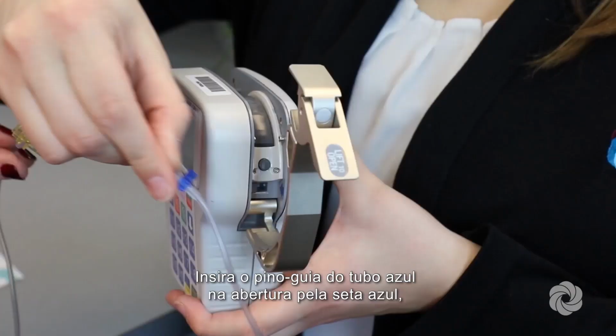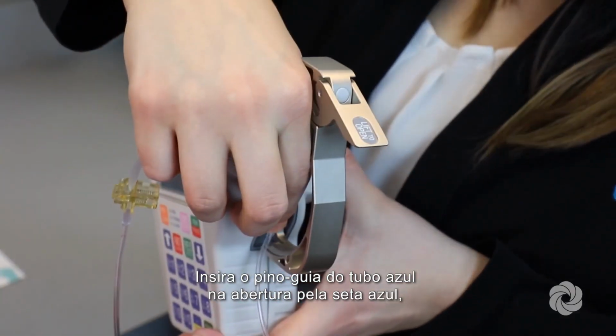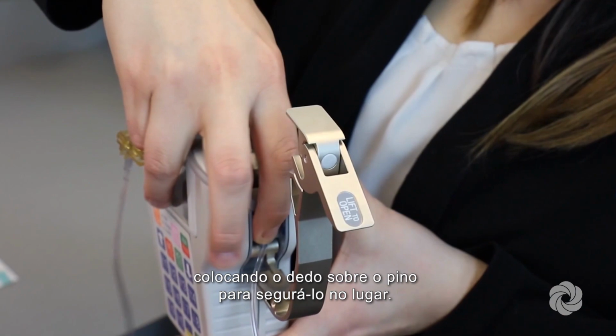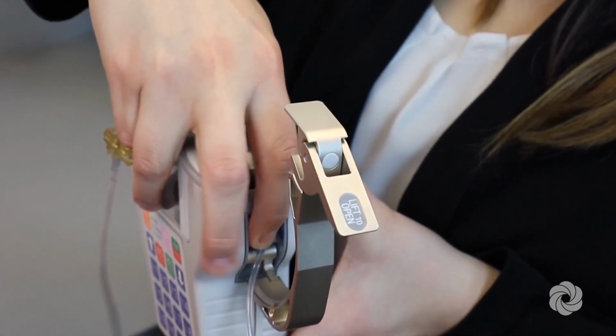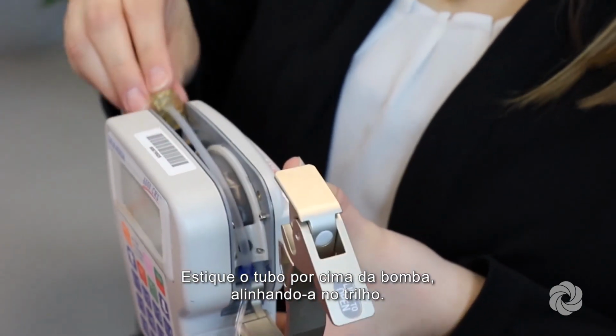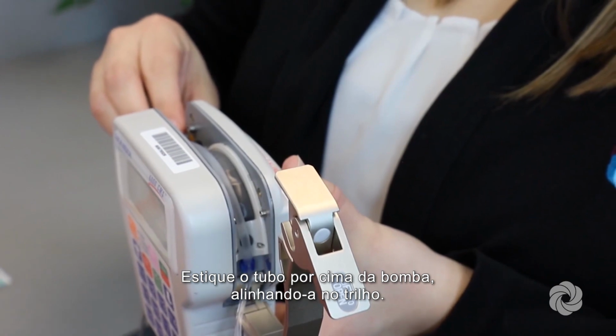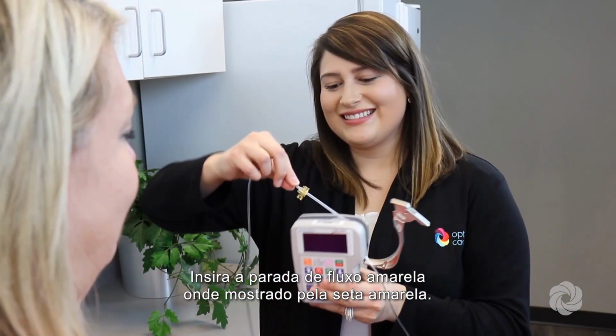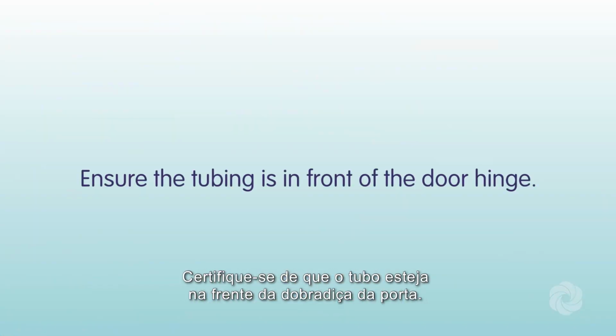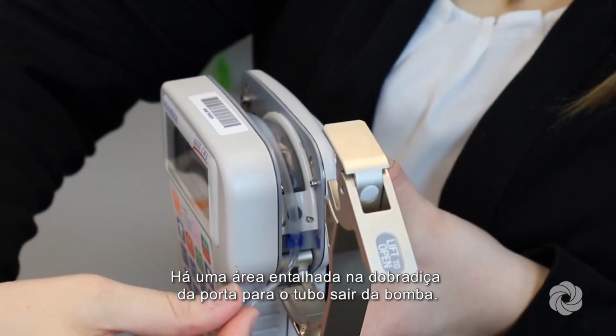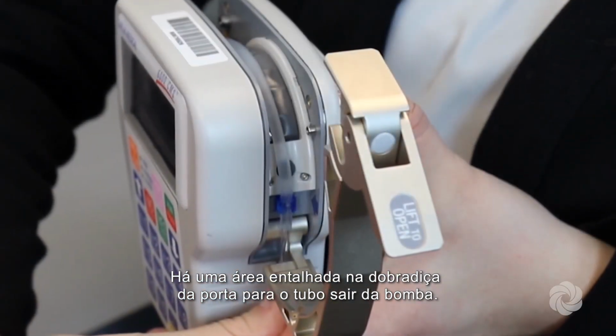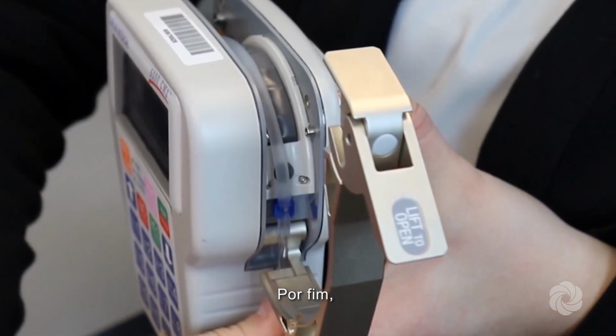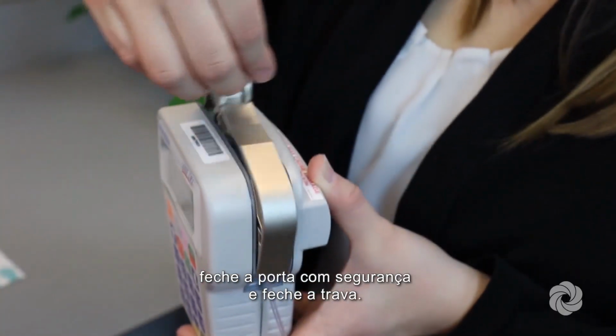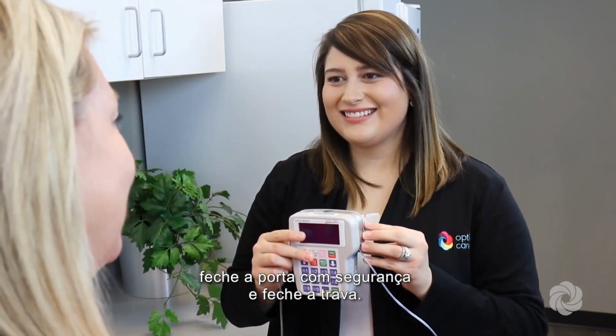Insert the blue tubing guide pin into the opening by the blue arrow, placing your finger over the pin to hold it in place. Stretch the tubing over the top of the pump, aligning it into the tubing track. Insert the yellow flow stop where shown by the yellow arrow. Ensure the tubing is in front of the door hinge. There is a notched area on the door hinge for the tubing to exit the pump. Finally, close the door securely and snap the latch shut.